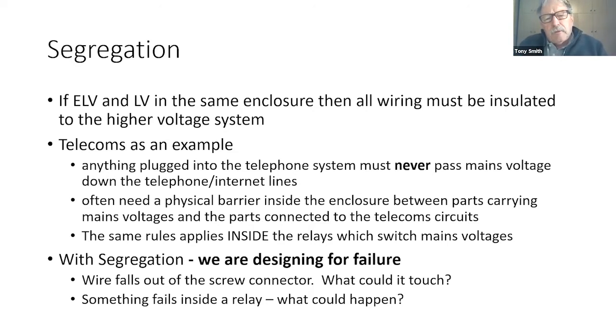So with segregation, what we're doing is designing for failure. You ask yourself the question - Richard had the DC on one end into a screw terminal and the mains on the other. The question would be, what happens if one of the mains wires came out of the screw terminal and was left floating around inside the cabinet? What could it touch? And the same applies inside things like relays - what if the coil wire broke? What could it touch if it came loose?